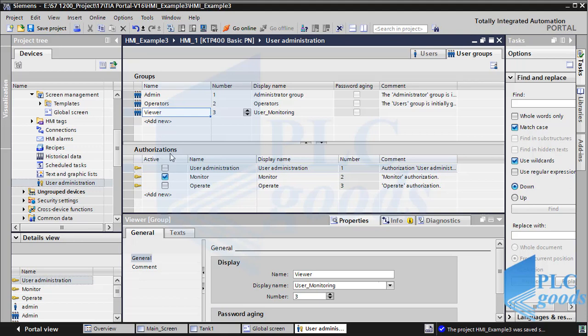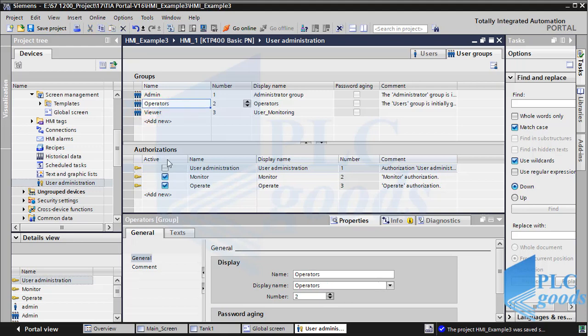In the second table we can determine each group's authorization. For example, the viewer group just monitors the industrial process on the HMI. Operators can monitor the industrial process and also do some work, such as press a button or change a number. The admin group has full accessibility.